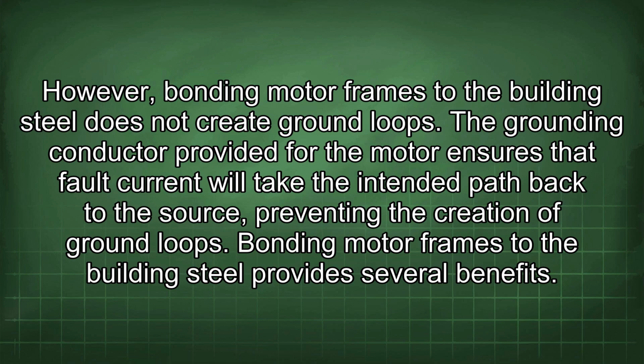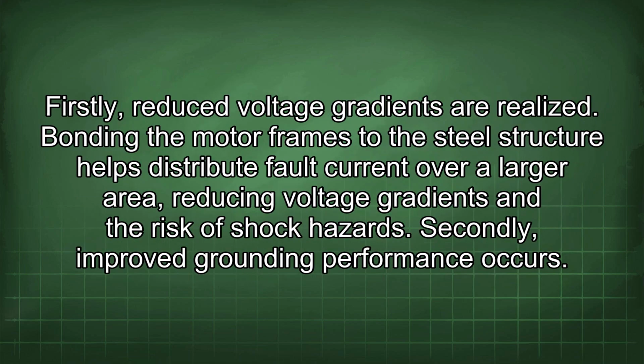The grounding conductor provided for the motor ensures that fault current will take the intended path back to the source, preventing the creation of ground loops. Bonding motor frames to the building steel provides several benefits. Firstly, reduced voltage gradients are realized. Bonding the motor frames to the steel structure helps distribute fault current over a larger area, reducing voltage gradients and the risk of shock hazards.